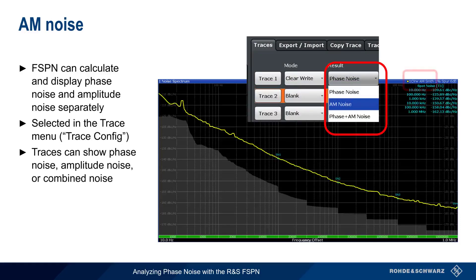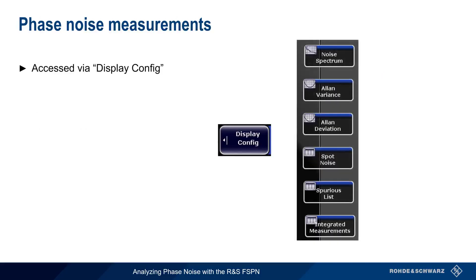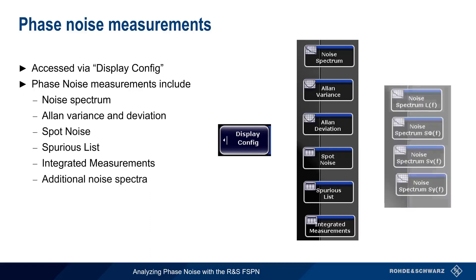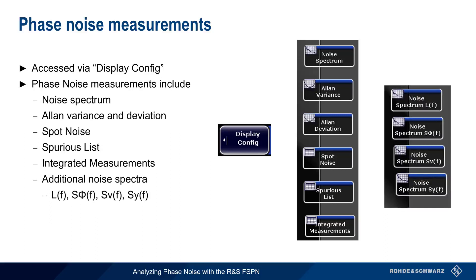The type of trace — here AM noise only — is shown at the top of the results display. The Display Config soft key brings up a list of the different phase noise measurement results that are supported by the FSPN. The first of these measurements is noise spectrum, which is the plot of phase noise versus offset that we've already covered. Additional measurements include Allan variance and deviation, spot noise, spurious measurements, and integrated measurements. The FSPN also supports additional ways of displaying noise spectrum, such as Sv(f) and Sy(f), but we won't be covering these in this presentation.